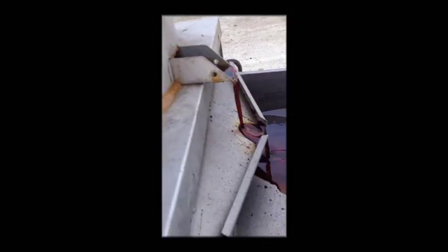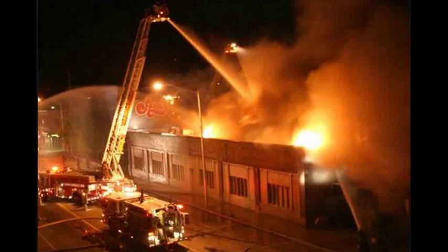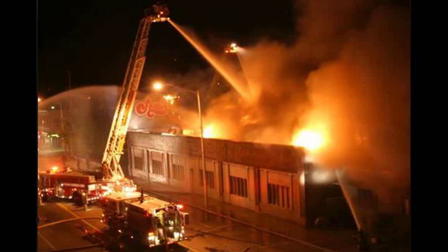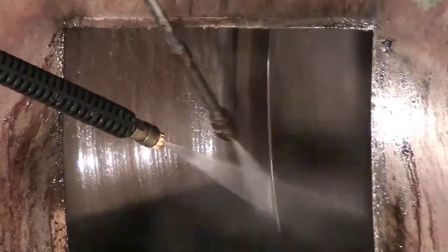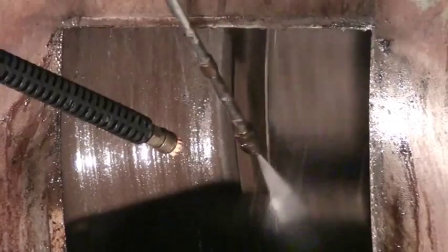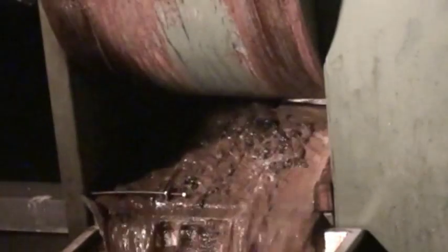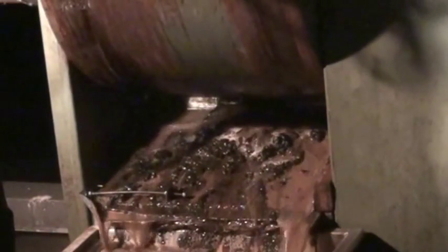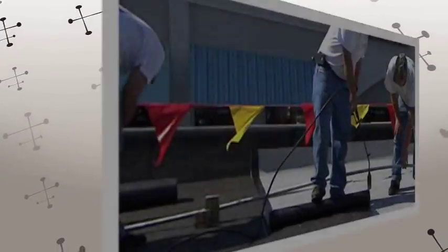But, did you know that the mandatory cleaning of your kitchen exhaust system that prevents the fire has a nasty effect on the roof, drain, and any HVAC equipment in the area? The general expected practice in the industry is to simply wash the fan down with hot steam, chemicals, often together at the same time. This creates a wave of hot, caustic, grease-laden water that is simply washed onto the roof, into the drain, eating the copper pipes in the building, and eventually spoiling our ecosystem with millions of gallons every year in North America. So how do we avoid spending money on absorbent material, roofing jobs, and harming the environment?